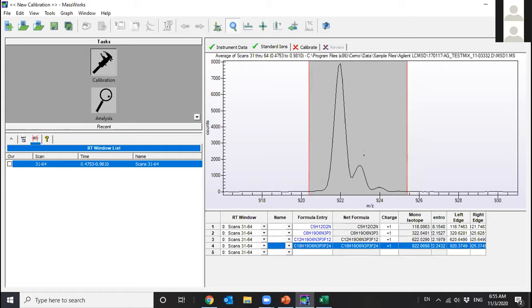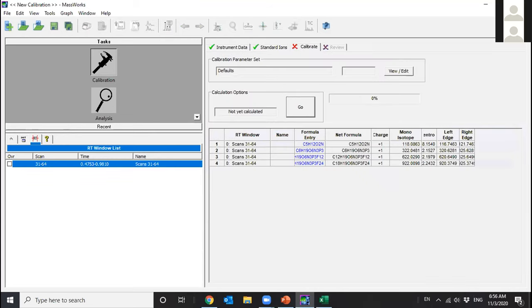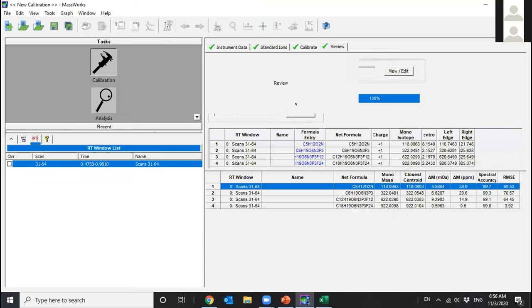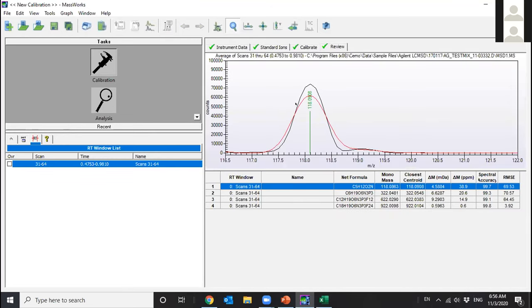And that's it. Those are the standard ions that we're going to use for the calibration, the four standard ions. And then you go to calibrate, you say go. And that's at the end, where you get the review page, and that review page would give you some indication of how well the calibration is working.